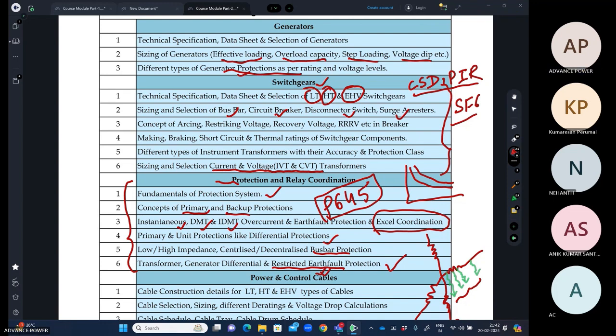We'll discuss in detail. Surge arrester again, it's a very complex selection phenomenon, because for every voltage level you should know the wave. So it is like the fast front wave. You might have heard of the lightning wave, which has a 1.2/50 microsecond characteristic. So how it is being drawn, how you have different voltages, like the chopped wave will have a different wave shape. Then the switching surge will have a different voltage wave. So for the different voltage waves, we will calculate, and see how the surge arresters are selected.